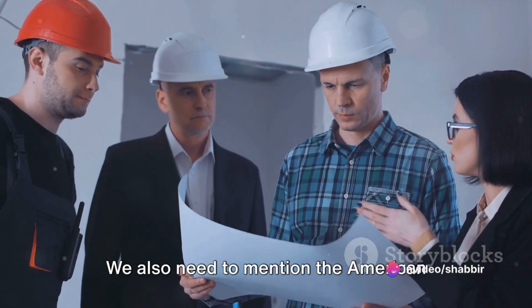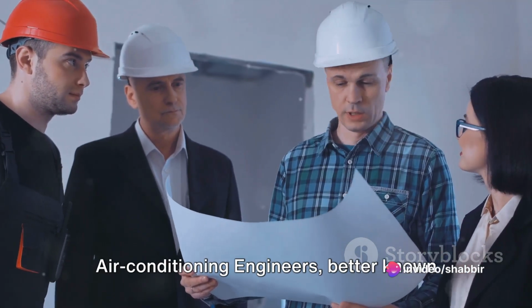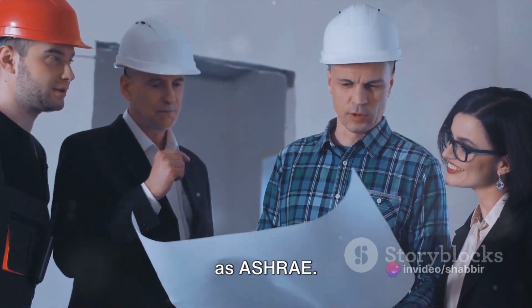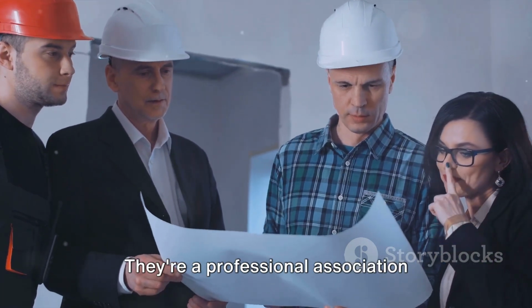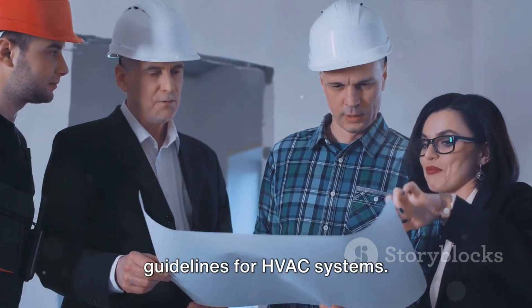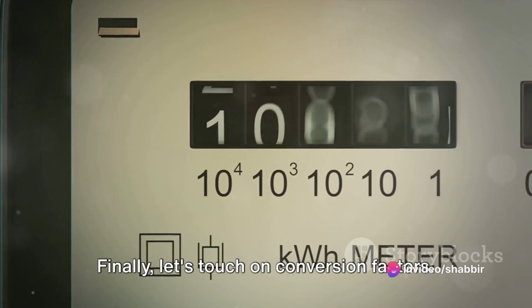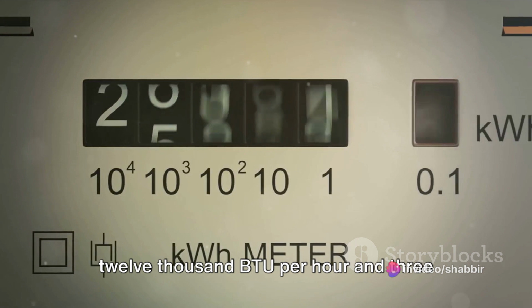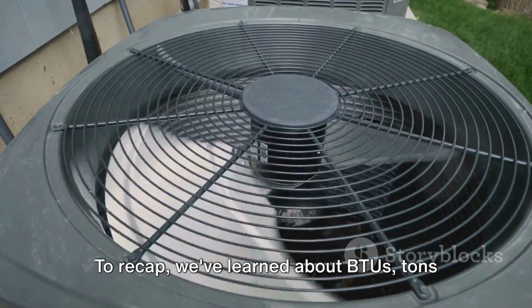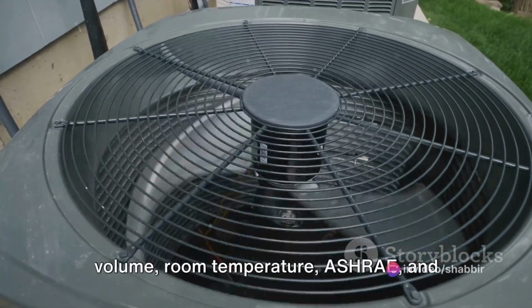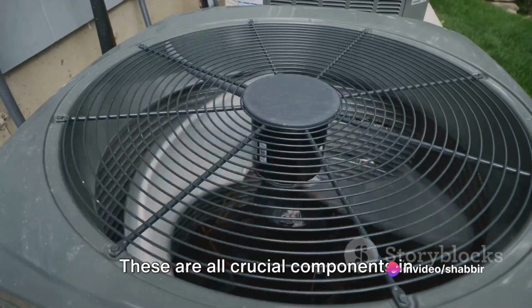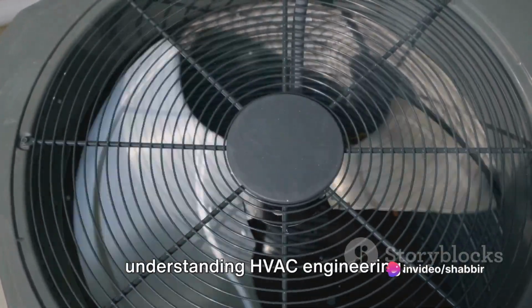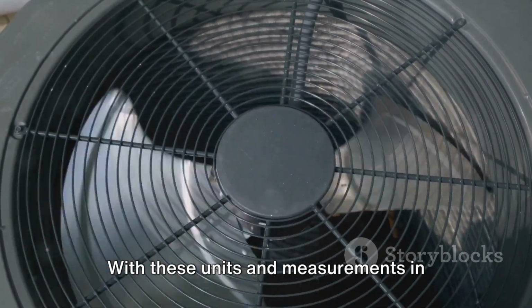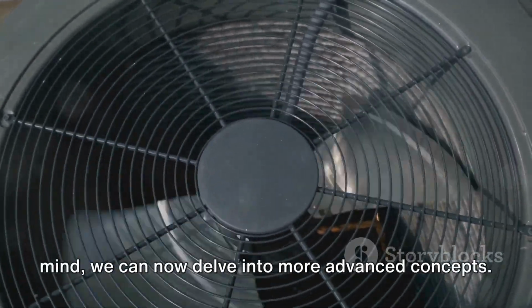We also need to mention the American Society of Heating, Refrigeration, and Air Conditioning Engineers, better known as ASHRAE. They're a professional association involved in setting standards and guidelines for HVAC systems. Finally, let's touch on conversion factors. For instance, 1 ton is equivalent to 12,000 BTU per hour and 3.516 kilowatts. To recap, we've learned about BTUs, tons of refrigeration, measurements of air volume, room temperature, ASHRAE, and conversion factors. These are all crucial components in understanding HVAC engineering. With these units and measurements in mind, we can now delve into more advanced concepts.